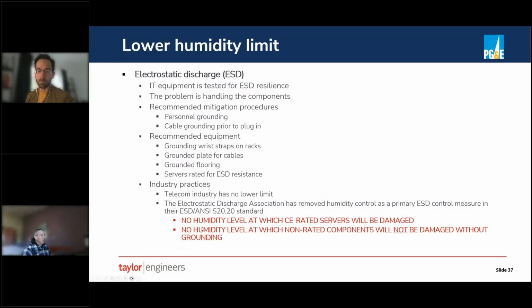And their conclusion was basically there's no humidity level at which a CE rated server will be damaged by electrostatic discharge. And I'll talk about what a CE rated is. And there's no humidity level at which a non-rated component will not be damaged without grounding. So humidification to address ESD is a false sense of security. It's not going to protect your equipment if you're working on the components within a server.